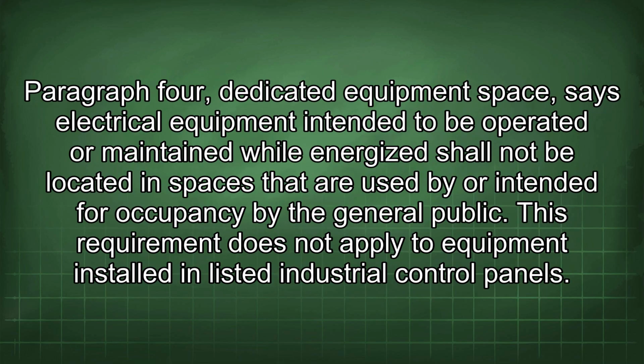Paragraph 4, Dedicated equipment space, says electrical equipment intended to be operated or maintained while energized shall not be located in spaces that are used by or intended for occupancy by the general public. This requirement does not apply to equipment installed in listed industrial control panels.